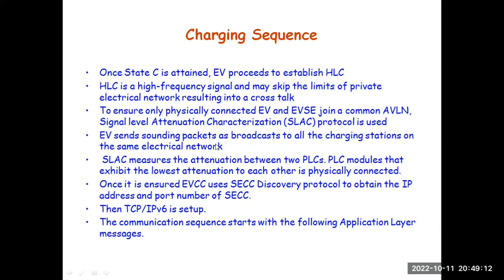This means the EV sends sounding packets as broadcasts to all charging stations on the same network. The charger with the lowest attenuation is determined, or the EV determines the charger with the lowest attenuation is the one connected to its network. SLAC measures that the one which is close to it, or connected to it, will have the lowest attenuation. The others' attenuation will be more. So SLAC measures the attenuation between PLC modules, and the one that exhibits lowest attenuation to each other is physically connected.